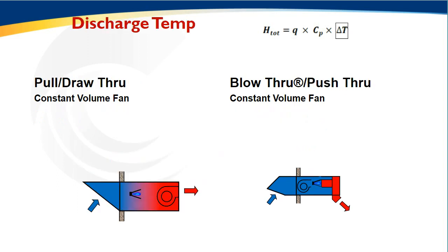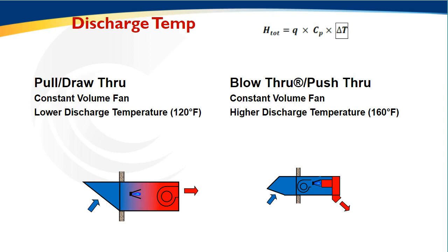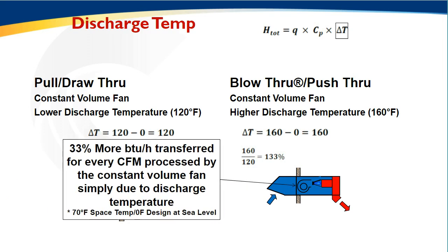What about the other key variable in this equation? Discharge temperature. Both systems are constant volume. We're going to hold our CFM standard from a fan volumetric perspective. But how about discharge temperature? Because, again, our blower is in the cold airstream and we can process warmer and higher discharge air, I now have about 33% more convective heat transferred per CFM by having the ability to turn up the discharge temperature. That means 33% more BTUs transferred for every CFM processed by the constant volume fan.